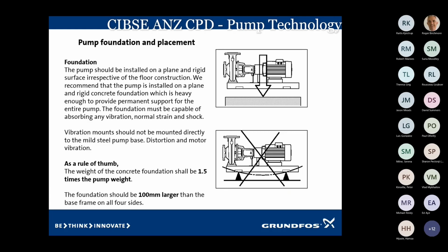If, however, you're placing that pump in a room above an office area, or above an area where you don't want any vibration to move down, this is where we'll bring in an inertia base. Just a rule there too, or just something to think about. When you pour your foundation, like you've done in the top box here, and you're going to mount the pump, make sure that the foundation is at least 100 mil larger all the way around.